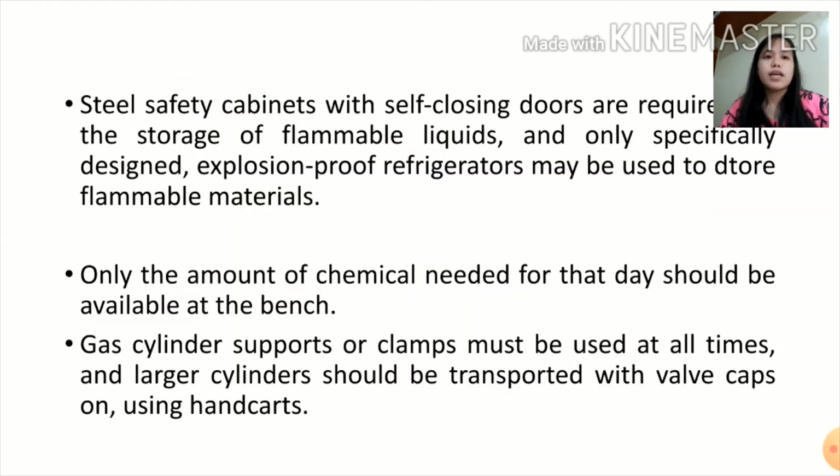Steel safety cabinets with self-closing doors are required for the storage of flammable liquids, and only specifically designed explosion-proof refrigerators may be used to store flammable materials. Only the amount of chemical needed for that day should be available at the bench. Gas cylinder supports or clamps must be used at all times, and larger cylinders should be transported with valve caps on using hand carts.